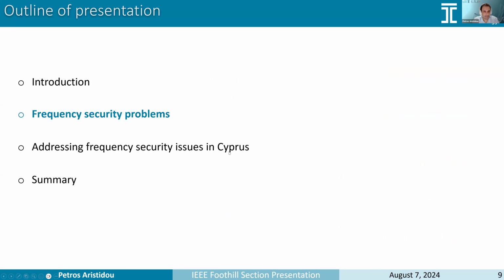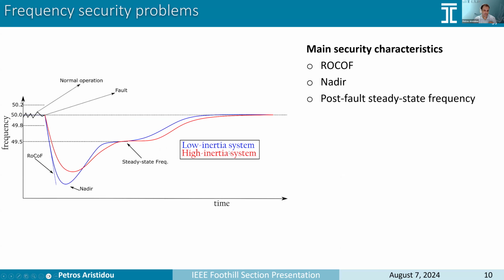So in this section, I'm going to go into more detail about the frequency security problems in low inertia systems. This is the same diagram that I had previously. I assume that we have a system that operates normally at 50 Hertz because we're in Europe. And then we have a sudden loss of generation here, a fault, which is a loss of generation.